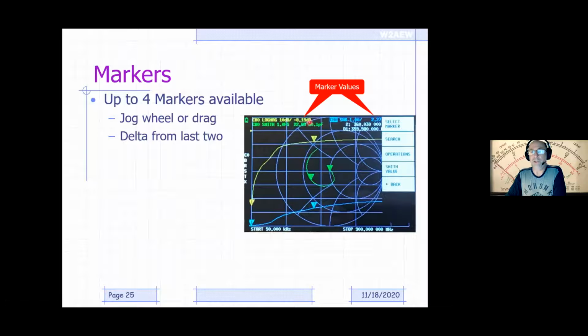So we see the yellow text right here on this first line, channel 0, which we know is the reflection port. When it's displaying log mag, this is the log magnitude of S11 of the reflection coefficient. Okay, so that's what this yellow trace is showing me here. The 10 dB per means that I've got 10 dB per division. The little arrow here means that this is the reference point, so that's 0 dB. Okay. And then the value here is actually the value where the active marker is. The active marker is shown right here as marker number 2. It's sitting at, in this case, 360 megahertz. And so that means that this point right here is 360 megahertz, okay, going across my frequency range here. And the value of this trace is minus 8.19 dB, okay, at that point.